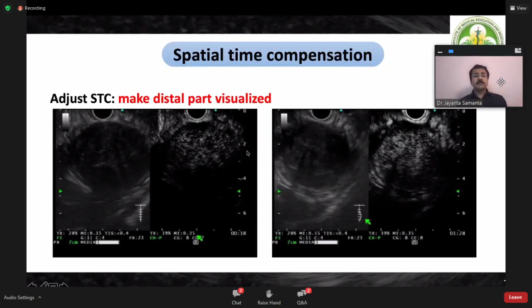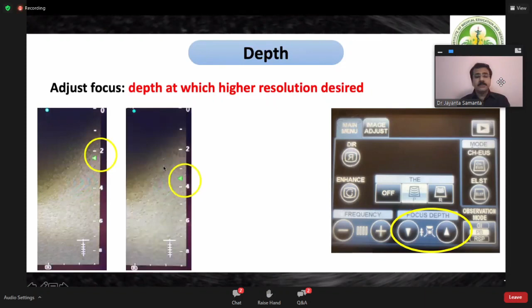Then comes the depth. Depth is another function where we use the focus depth in order to increase the resolution at the desired depth. So basically, ultrasonic waves behave just like light. We have all read in the physics of light that there is a focal point. So what we do over here is we set the focal point at specific levels where we want the resolution to be the best. As we keep on increasing the focal depth, that is the place where we get the best resolution of the image.